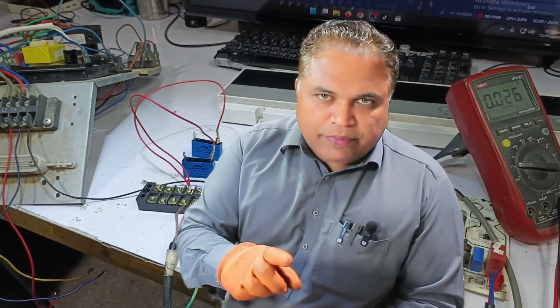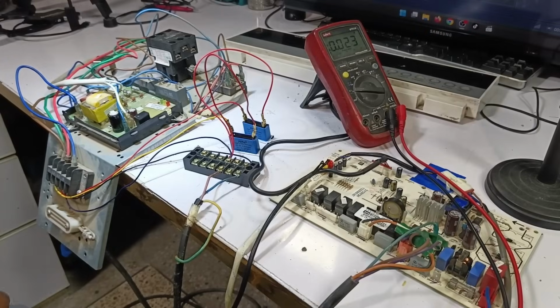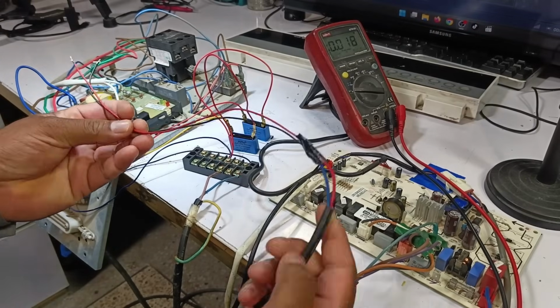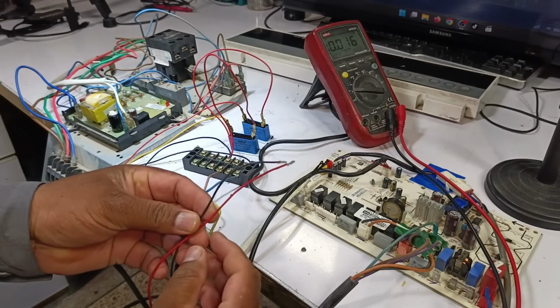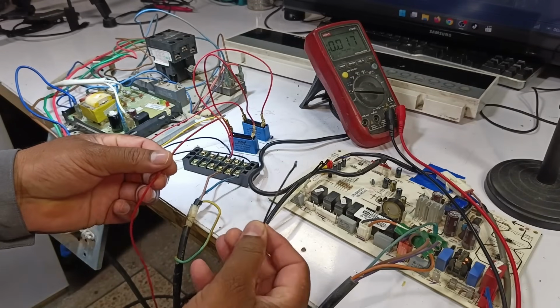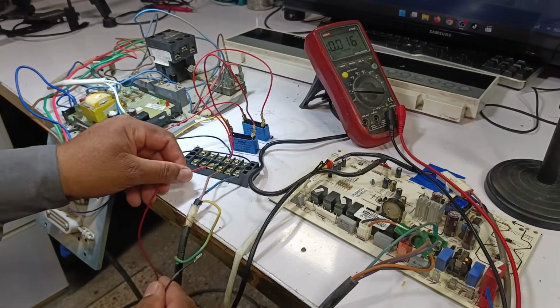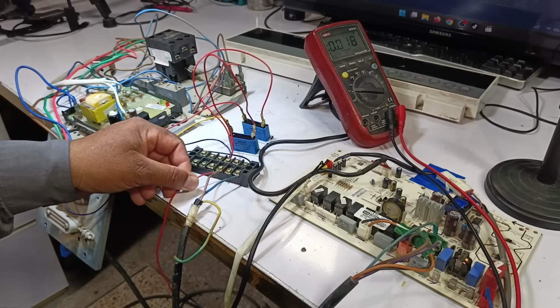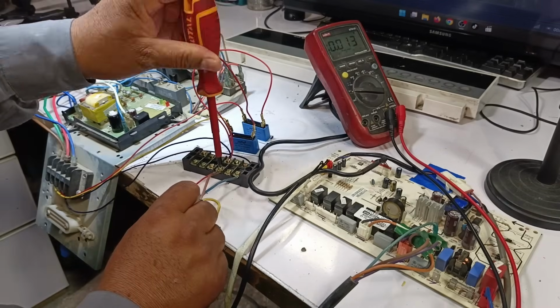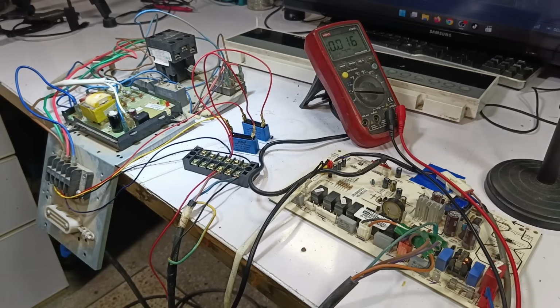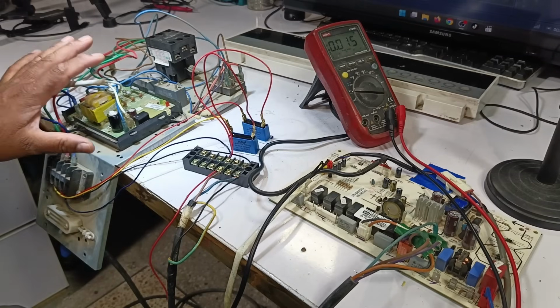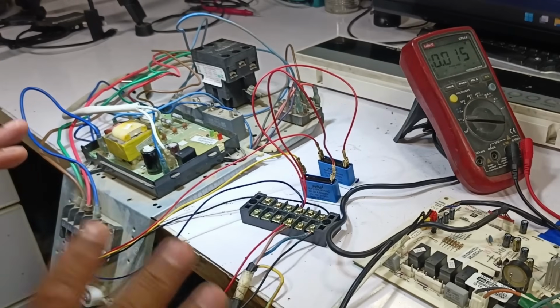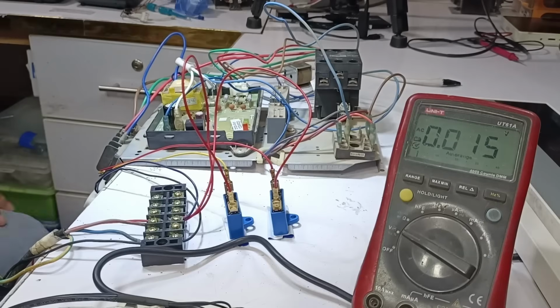Now, I will reconnect everything exactly the same way I showed you earlier, and after that, I will power on the PCB. Before supplying power, here I have the wire for the indoor PCB. We will also connect it so that the indoor unit can receive the supply as well through the same main single-phase power source we prepared. At this point, all the connections are properly set up. The indoor unit is now properly attached to the outdoor unit. Now I will turn the system on.